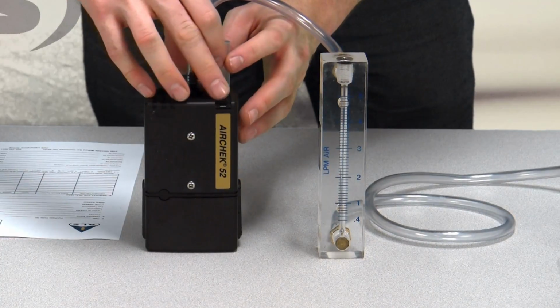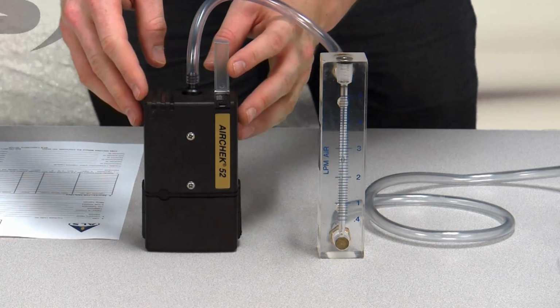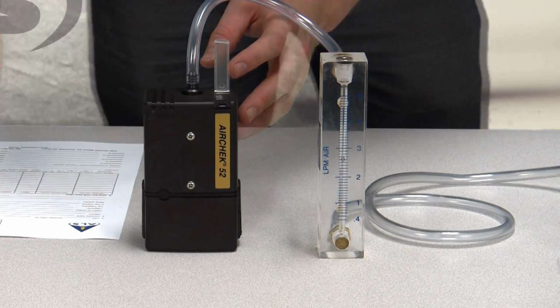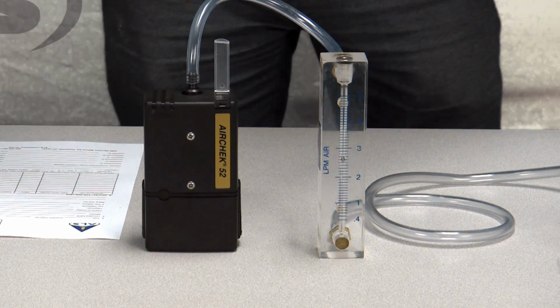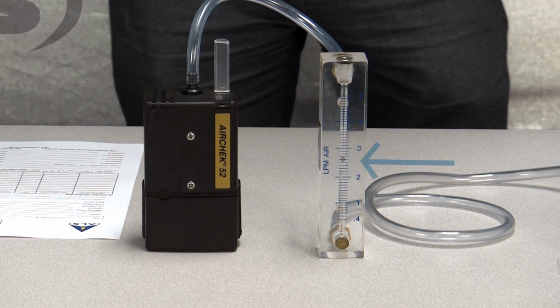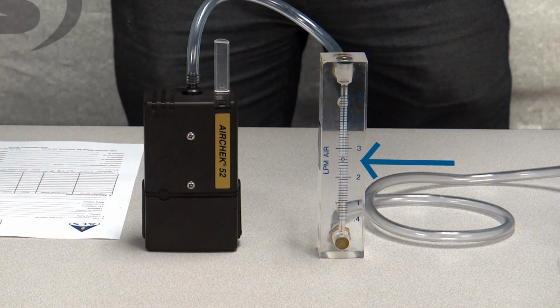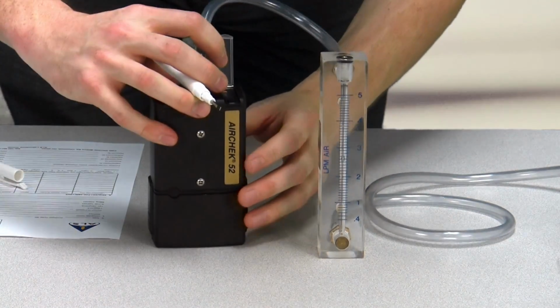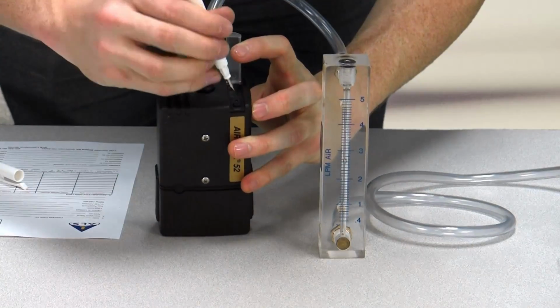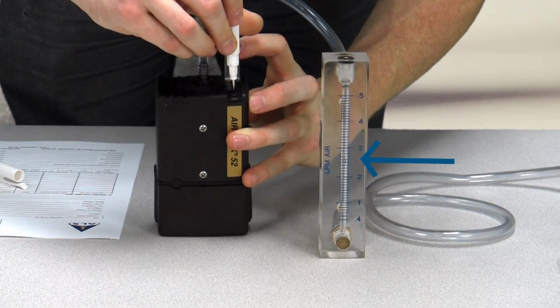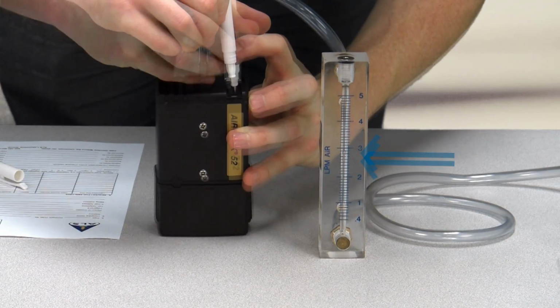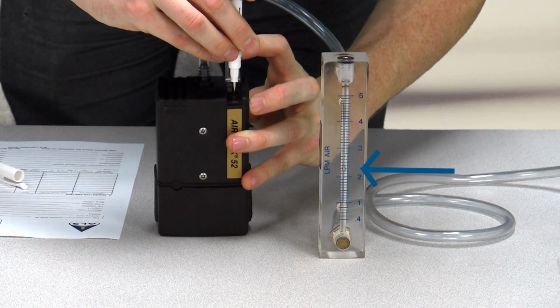Lift the pump's control cover and start the pump using the on-off button. Make sure to read the graduated lines of the field rotameter at eye level and that the silver bead is centered at the appropriate flow rate. Adjust the flow rate by using a screwdriver on the set screw next to the on-off pump button by turning it clockwise to increase flow and counterclockwise to decrease it.